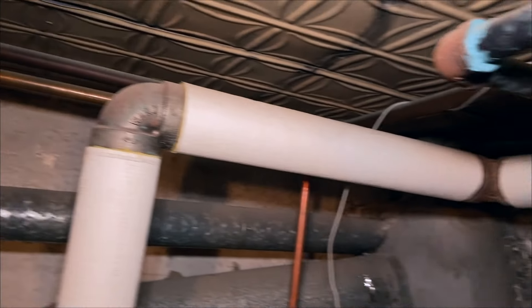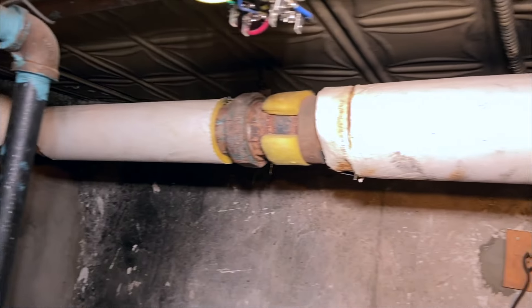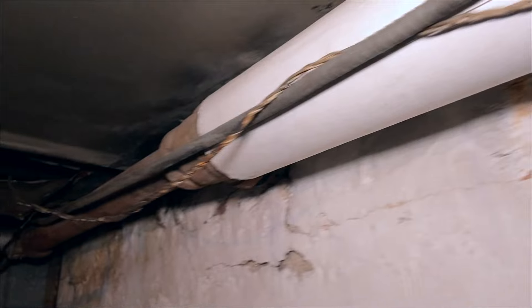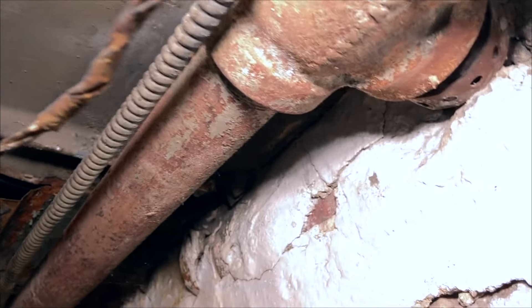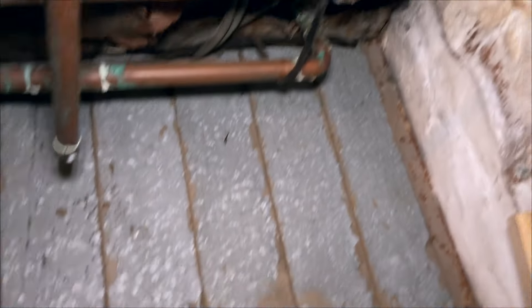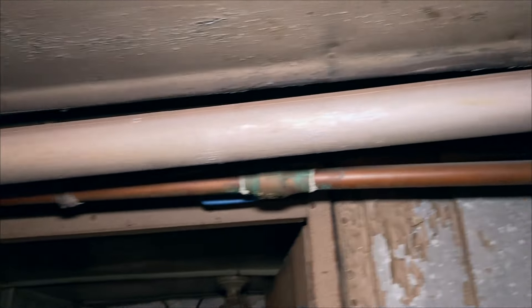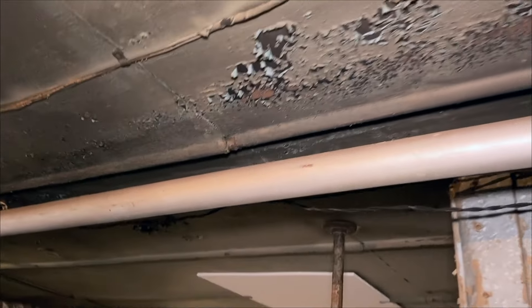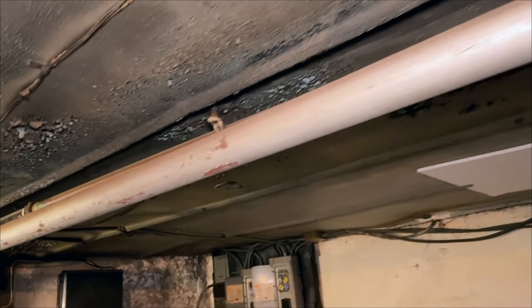Here's the main going up and it's going toward the back of the house. There's a garage back there with a heated space above it — there are bedrooms above the garage. It comes through the partition and starts to feed going towards the garage. There's a T connection going toward the front of the house, all the way to the front of the house where there is another set of returns. We are going to the extreme rear of the garage and you're going to see a riser going up there, a couple of risers in the rear before it drops down onto the concrete.